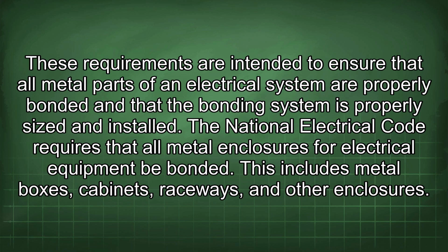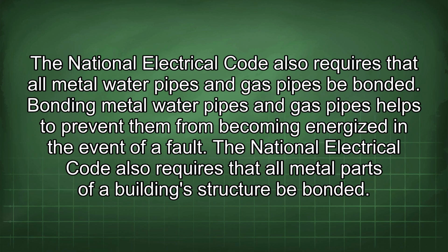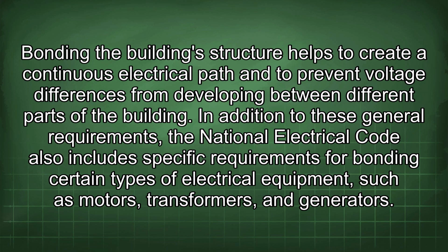The National Electrical Code requires that all metal enclosures for electrical equipment be bonded. This includes metal boxes, cabinets, raceways, and other enclosures. The National Electrical Code also requires that all metal water pipes and gas pipes be bonded. Bonding metal water pipes and gas pipes helps to prevent them from becoming energized in the event of a fault. The National Electrical Code also requires that all metal parts of a building structure be bonded.